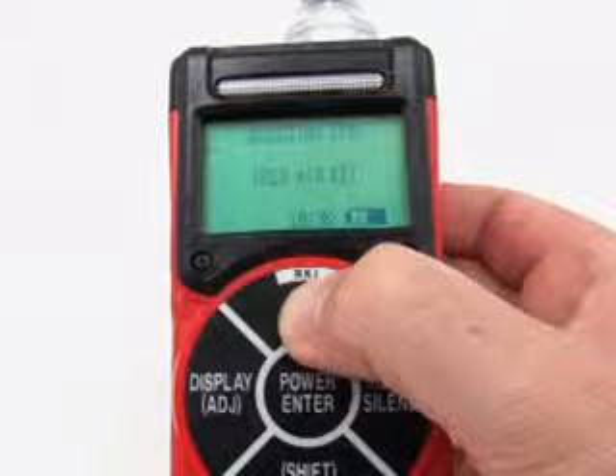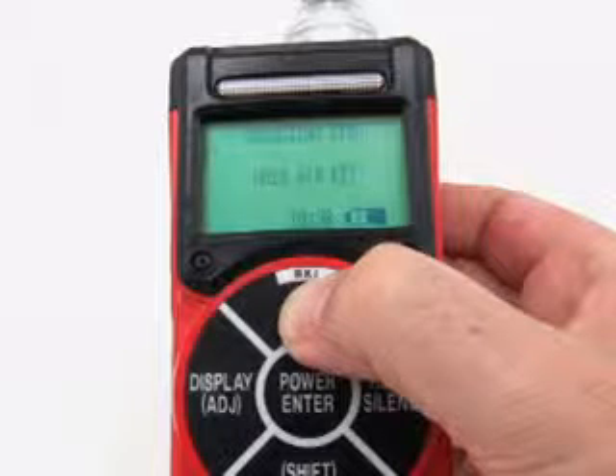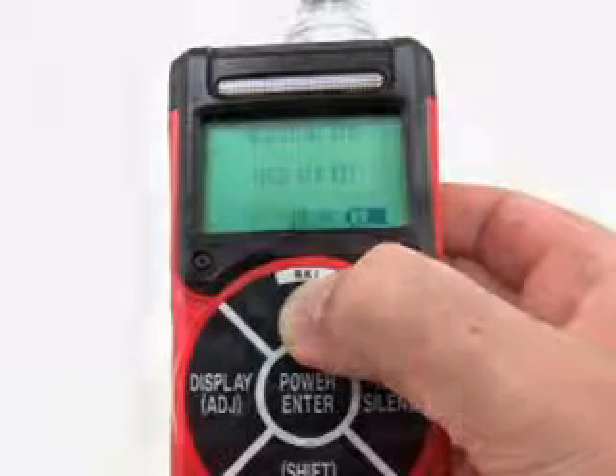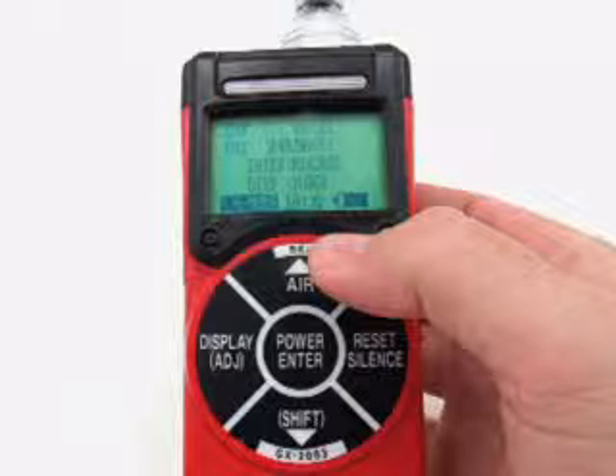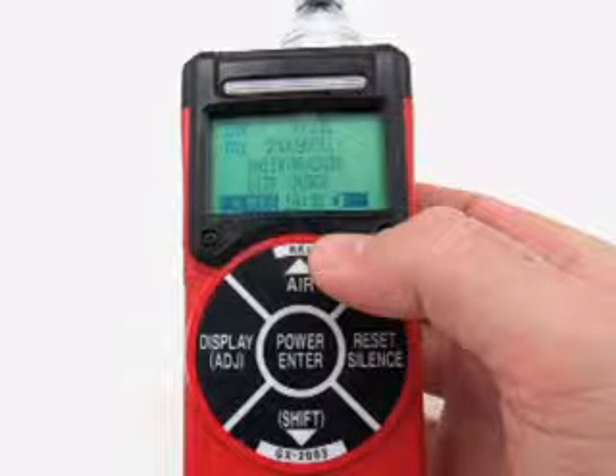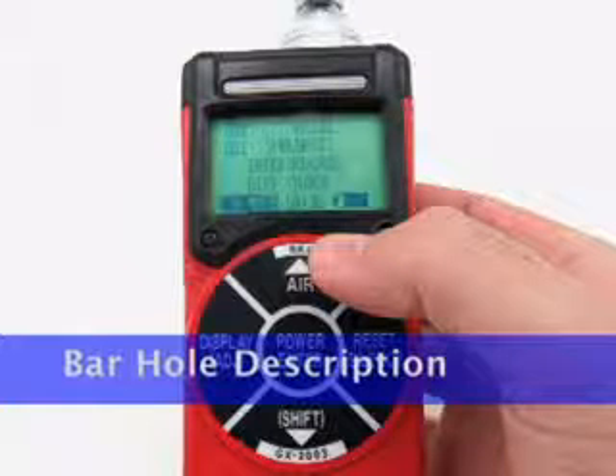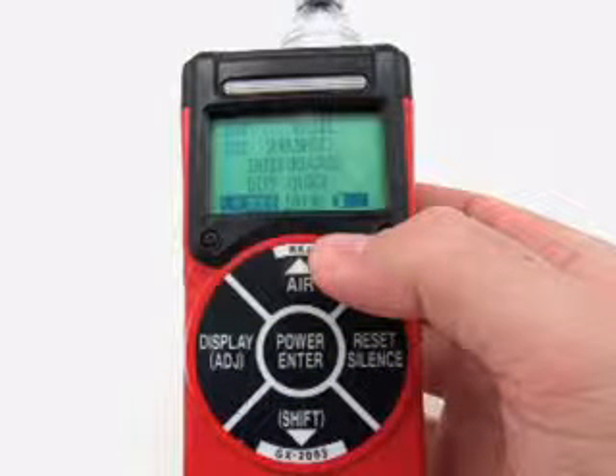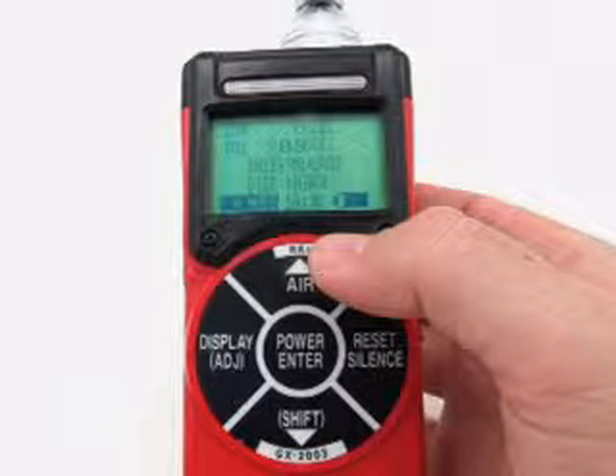Continue to hold the air button until the display prompts you to release the air button. The GX2003 will set the fresh air reading for the methane and oxygen channels. Startup is complete, and the unit is now ready for bar hole testing. In bar hole mode, you can initiate sampling for a fixed time period to monitor for methane and oxygen in a bar hole. The factory set time is 30 seconds.